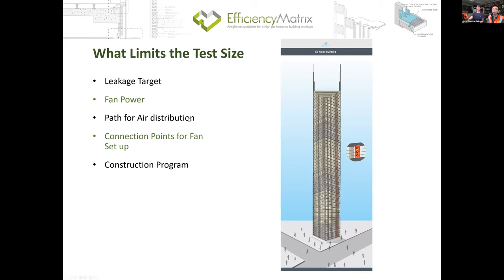What actually limits the size of a building that can be tested is listed on the screen here. Number one, leakage target. It is very, very different to test a huge building with a target of 20 meter cube per hour per meter square allowable leakage, like what is in Green Star, or testing a passive house. To test a building as big as the Rialto Tower, if it meets the requirement of passive house, is no harder than testing an aquatic center with a 20 meter cube per hour per meter square leakage target, because of the ratio of the surface area to the leakage.